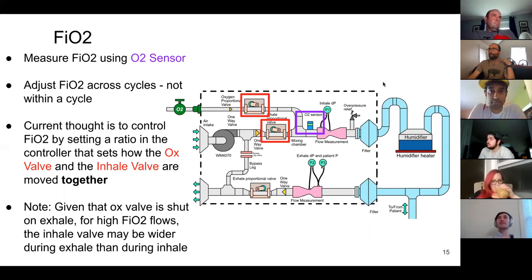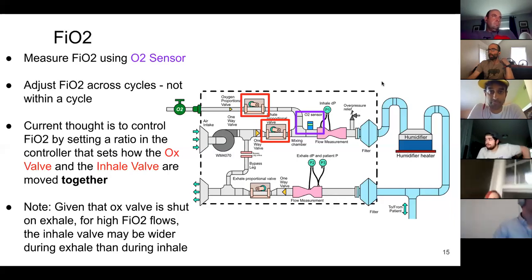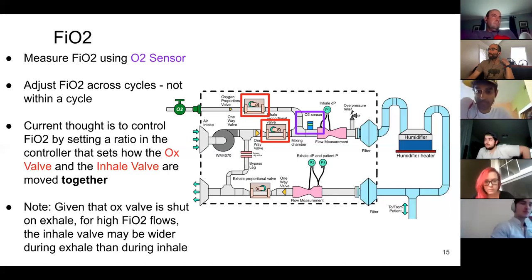Yeah, I just had a comment here. So you're using a galvanic cell for the O2 sensor, right? For now. Okay, so just for historical context, in other ventilators, the O2 sensor is almost never used as part of a closed loop or long-term adaptive strategy. It's just used as a monitor only. I'm not sure what the reason is, but it might have to do with the fact that they wear out. They typically last about 12 months before you have to replace the O2 sensor, and so they're typically not used as part of any control routines.